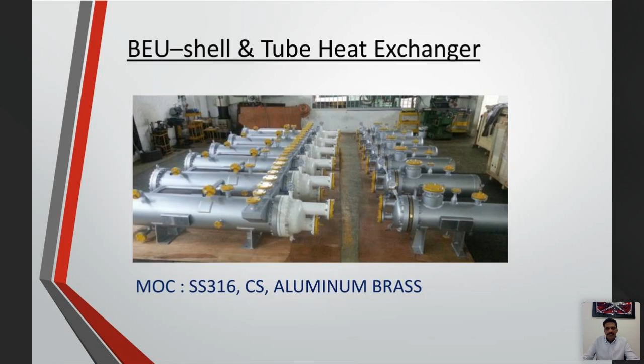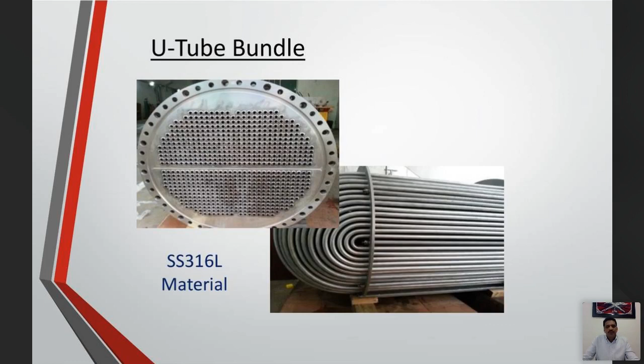When you talk about tubes, you can find U tubes also, because sometimes the thermal expansion is very big, and even you put 3 bellows or 5 bellows or 6 bellows, still the thermal expansion cannot be taken care of. But no choice, you have to use it for the thermal expansion. Then we come out with U tubes. The U tube has a free thermal expansion. That's why people use U tube bundles.